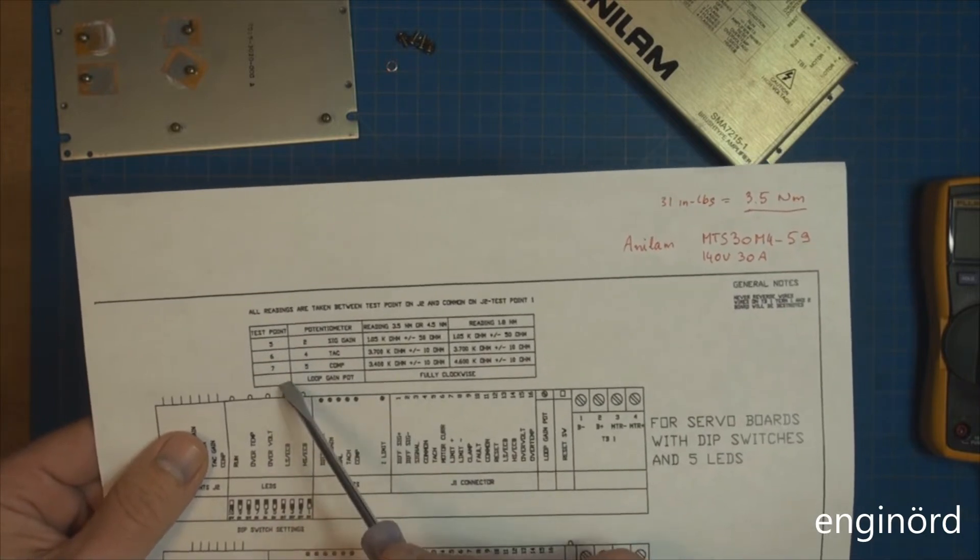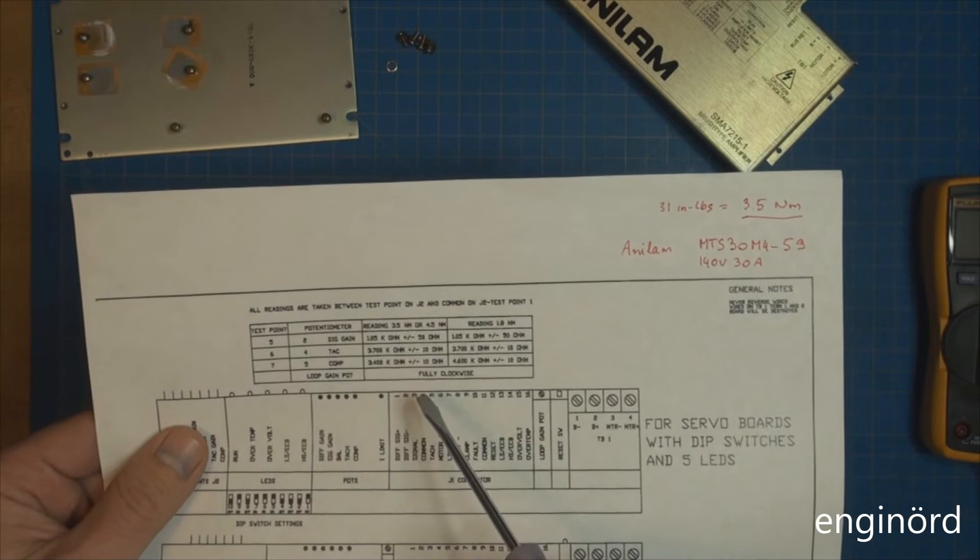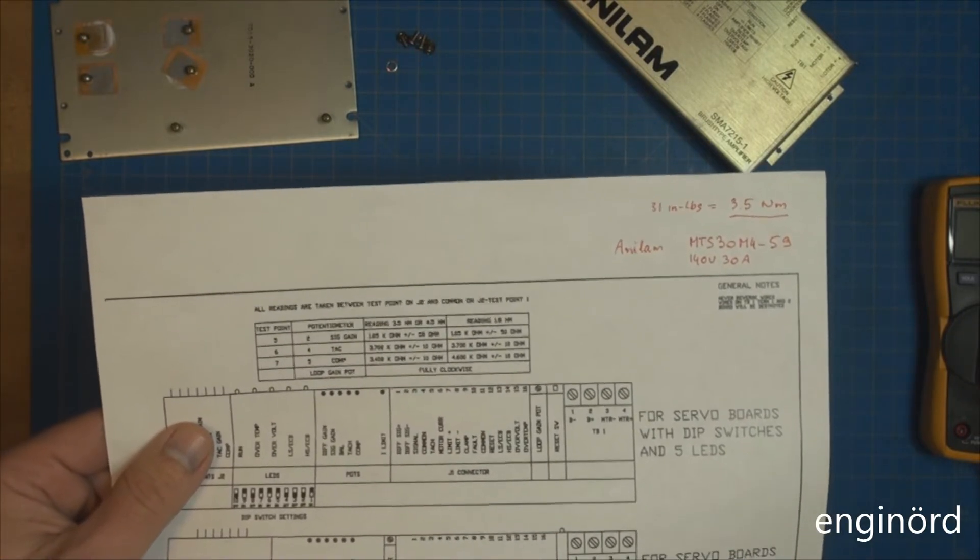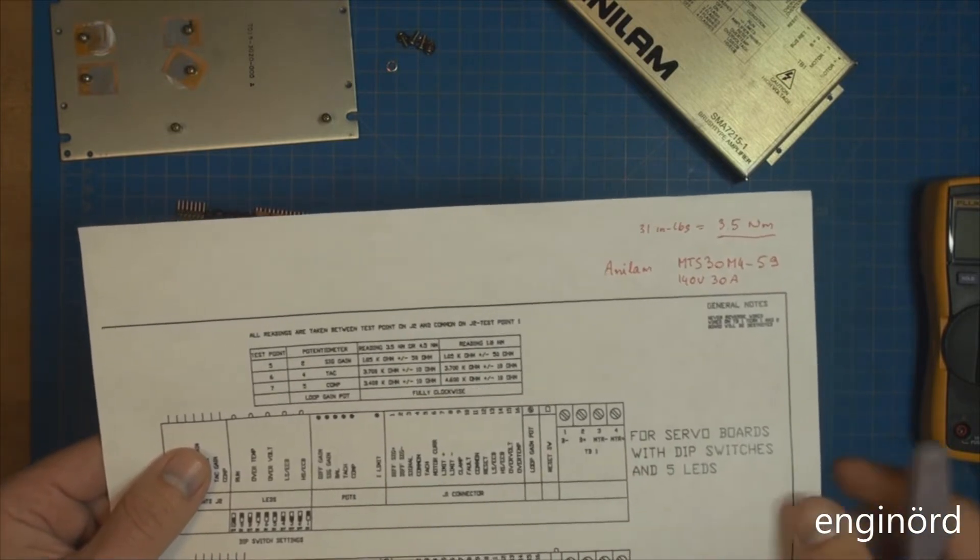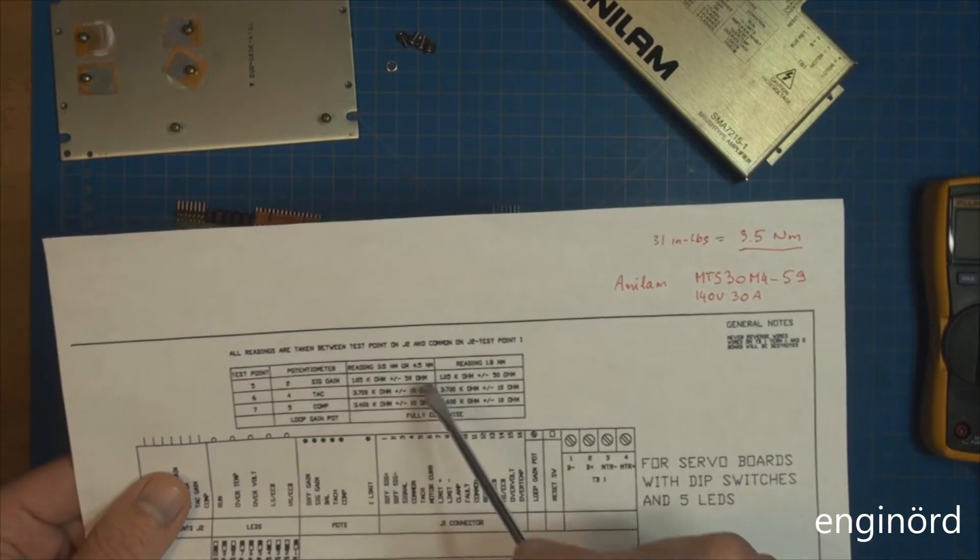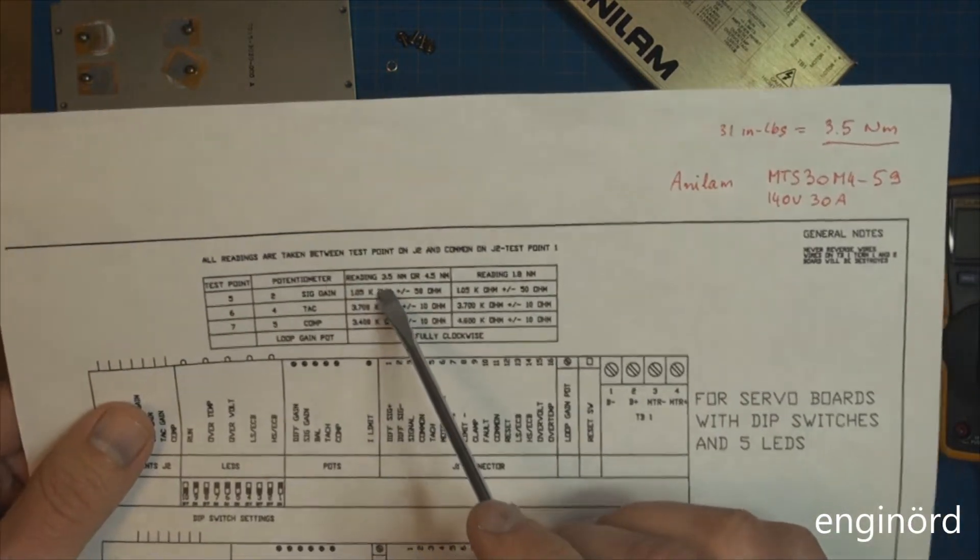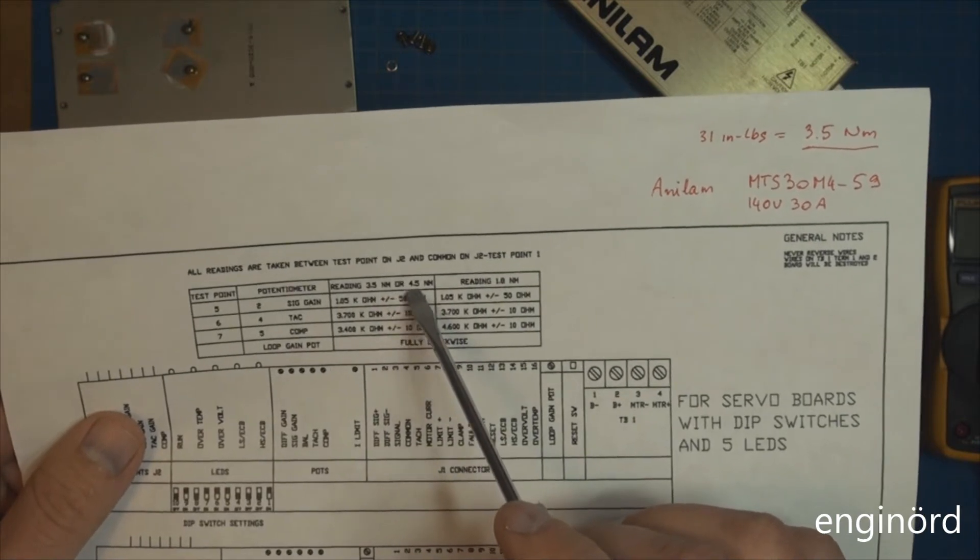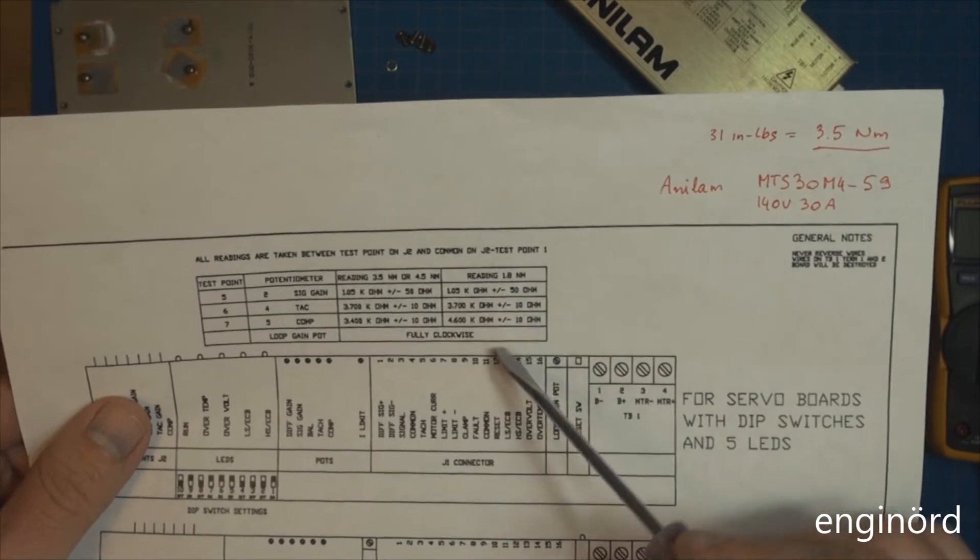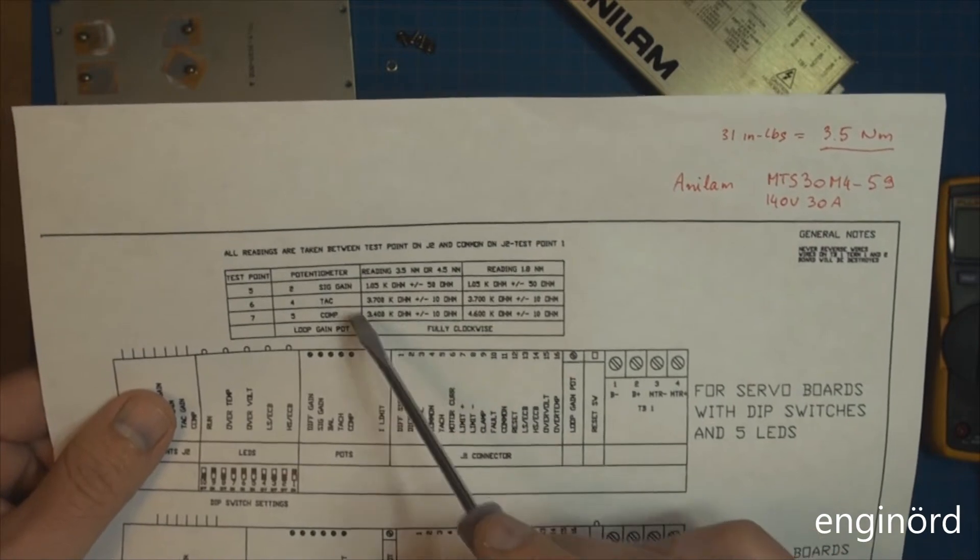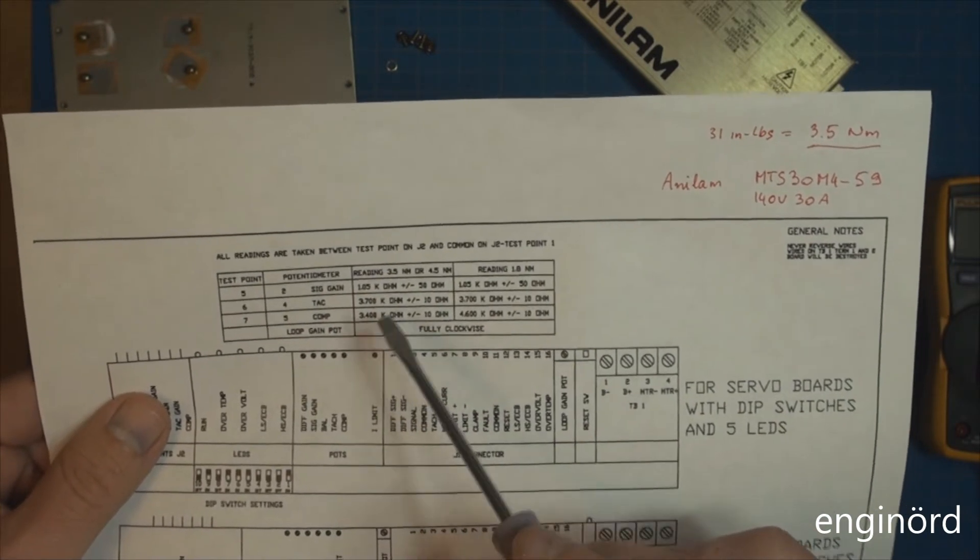It says all readings are taken between test point on J2 and common on J2 test point 1. There's basically three test points. This will set up the servo amp to drive the motor properly. There's two columns - a reading for 3.5 newton meter or 4.5 newton meter, and a reading for 1.8 newton meter. This is a small motor and these are larger motors.